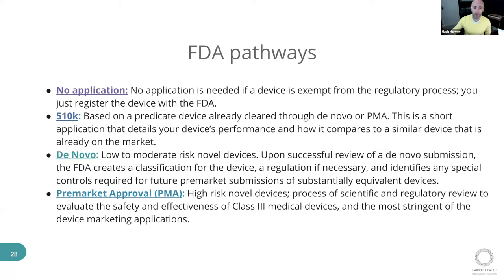Typically with new devices, you need to do a de novo application if you are low to moderate risk. If you are high risk, you need to do the full whack, a PMA. This can take 2, 3, 4 years to get to market, and the FDA will scrutinize every single piece of evidence that you possibly have.